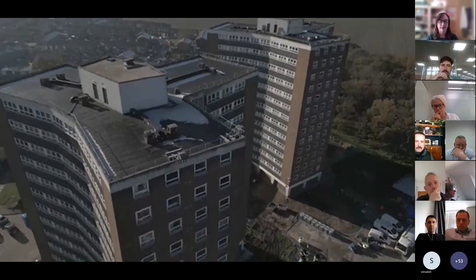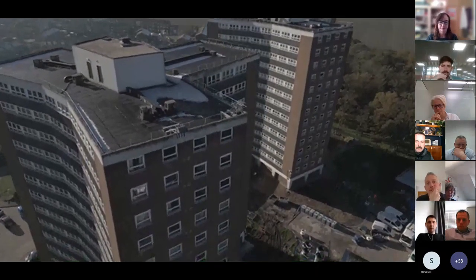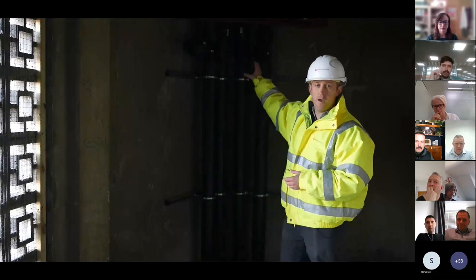At this stage, we're installing the riser pipework to connect the ground arrays into the individual apartments. So here in the corner, we've got the risers that come up through each floor. We have a fusion weld tee at the top here, where we tee off to provide the flow and return to serve the laterals, which then serve all of the individual heat pumps on this floor.